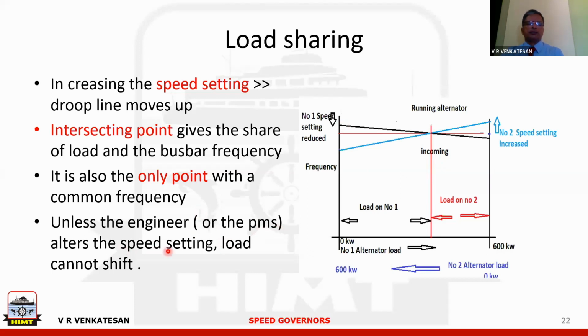How do you change the speed setting? By the speed of the motor. Unless the speed setting is changed, unless these 2 points move, the load cannot shift, because the 2 alternators cannot run at any other point. They can run only here. Because of this, there will be no random shift of load. We will give it stability. That means if I want this generator to take 400 kilowatt, it will continue to take 400, and this will take 200, and it will remain like this. Without this, you will get instability. That you will see in the coming slides.